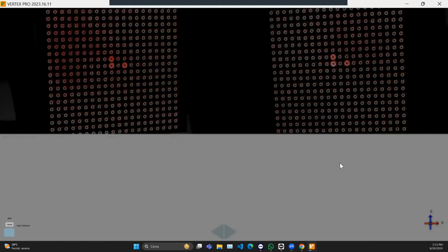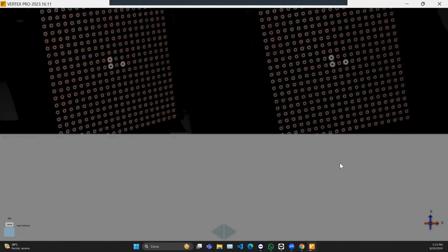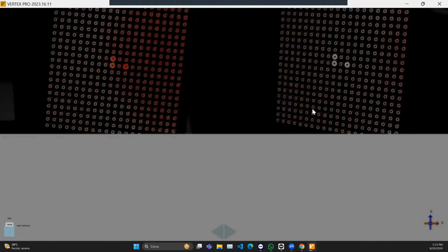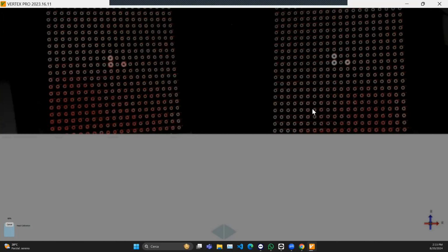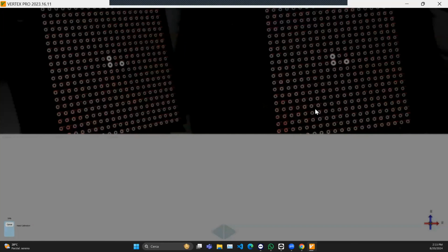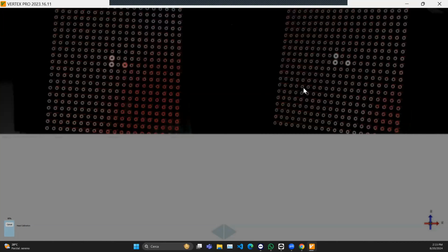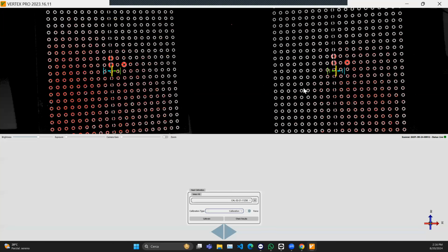So for each couple of images, we are detecting the centers of the circles. You see that the software is finding all the circles. I'm doing nothing, I'm just looking at the screen. Thanks to the 2-axis rotary table, the software is able to do the calibration automatically, so I don't have to define positions or other things. Just wait for the results. At the end of the calibration, it will be possible to see its quality, because we always compare the recalculated centers with the original centers and give the remaining error.